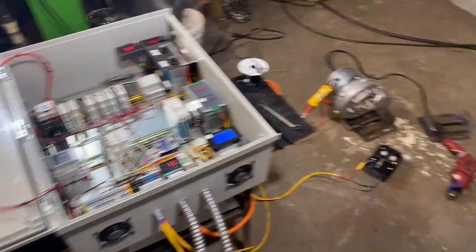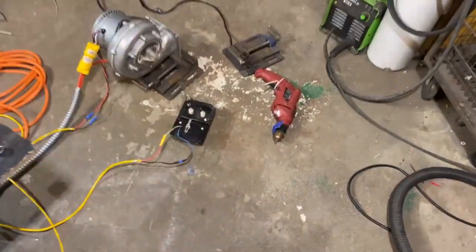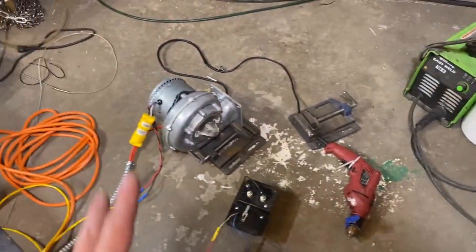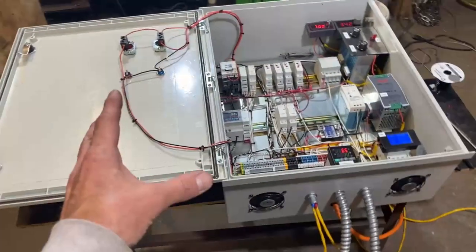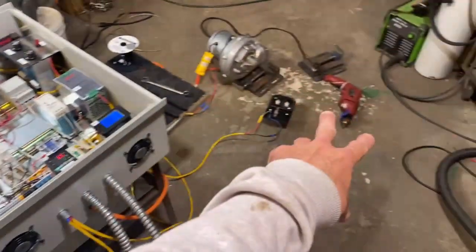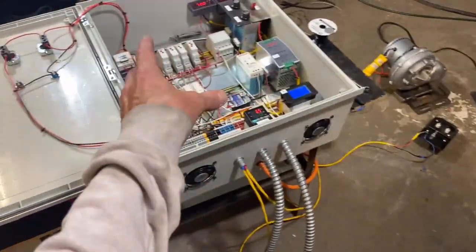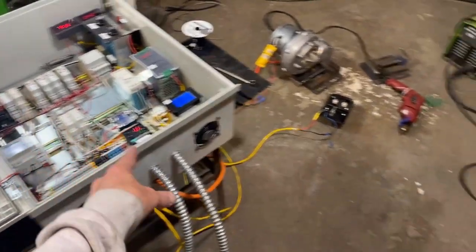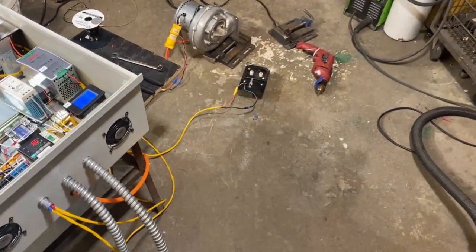Okay so we're going to do one last simulation here. We have the igniter and this drill is going to simulate the fuel pump and we have the blower. We're going to hit the switch. We're going to see the fuel pump and the blower kick on low for the set period of time in this case being 10 seconds. The igniter will also be running.